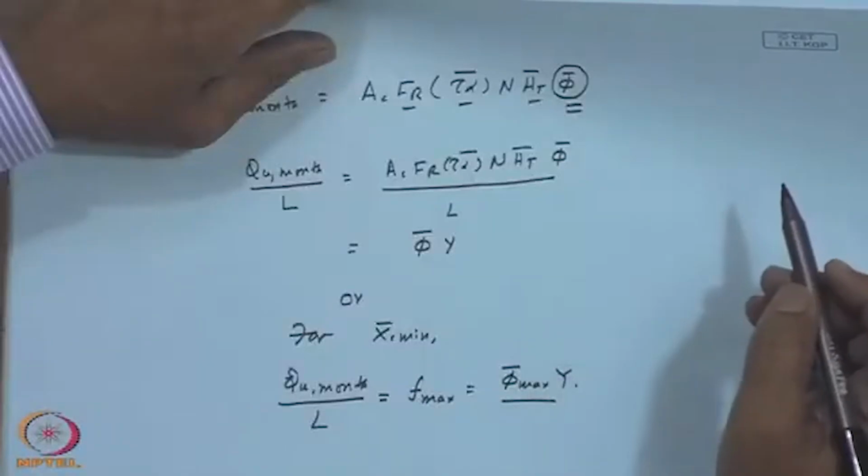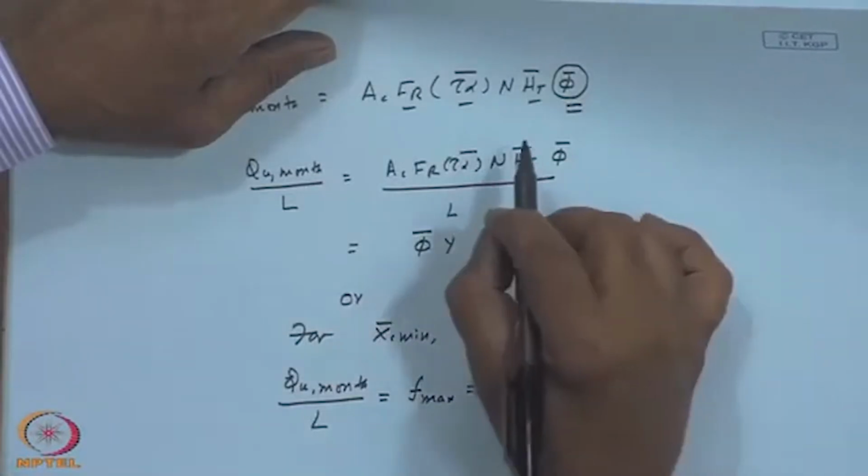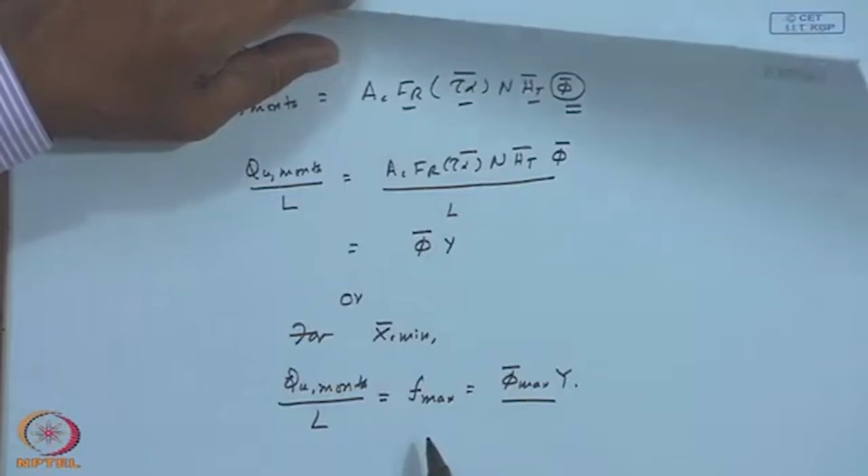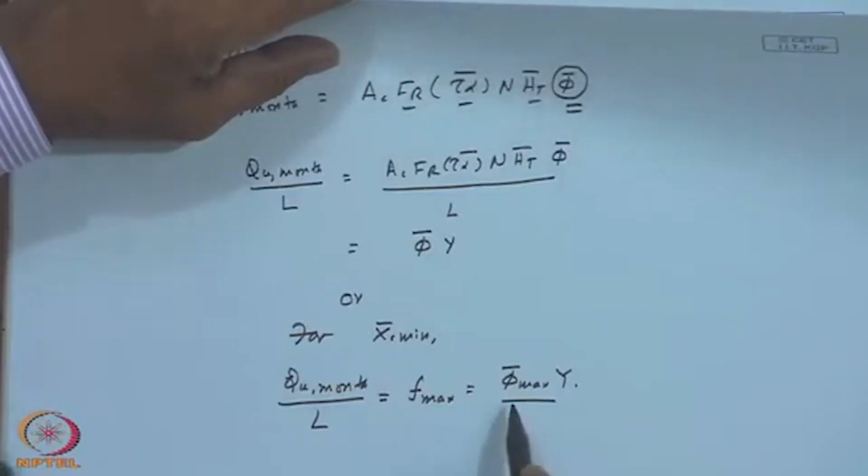If all the energy delivered by the solar collector is going to meet the load, there are no losses in the pipelines, there are no losses in the heat exchanger or in the tank, then this will be the solar load fraction that will be met. So, in one sense, simple knowledge of utilizability can give you an estimate of the possible maximum solar load fraction. This is almost an ideal number that one gets.